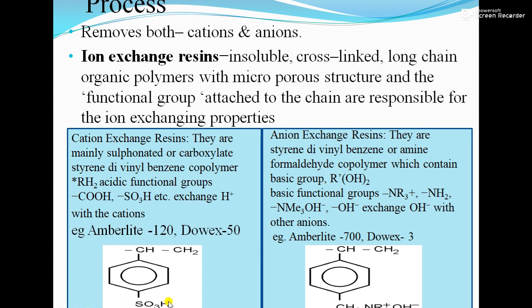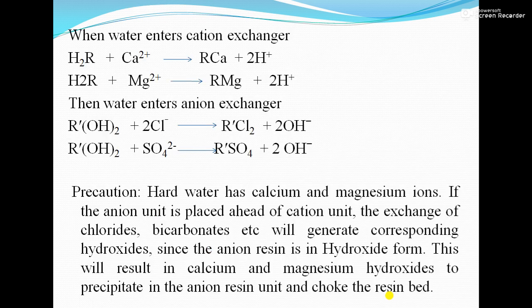The hydrogen is loosely bound to the sulfonic group and can be exchanged with calcium and magnesium. Similarly, the hydroxide is loosely bound to the ammonium salt group and can be exchanged with chlorides, sulfates, or nitrates present in the water. In the reaction, for the cation exchanger resin RH₂, calcium²⁺ from the water is exchanged: H₂ is replaced giving RCa + 2H⁺. Similarly, magnesium is converted to RMg. So cations get exchanged in the first compartment.